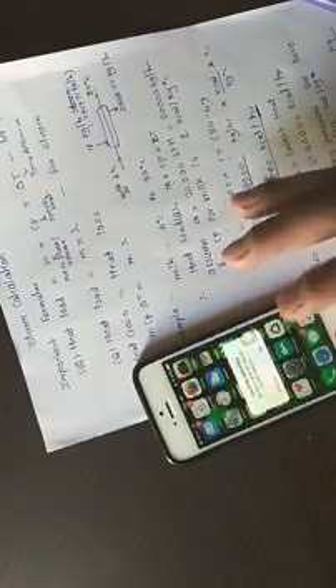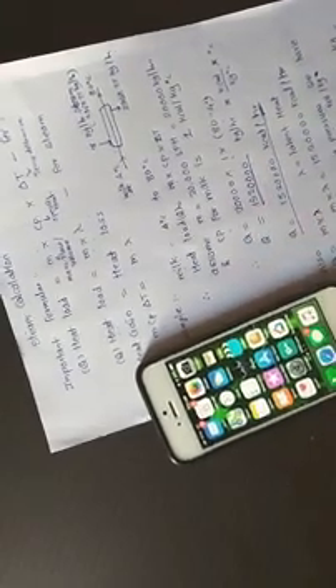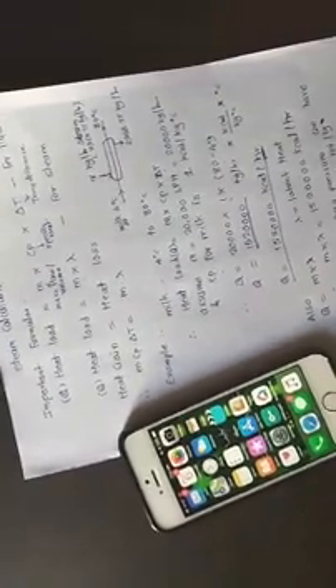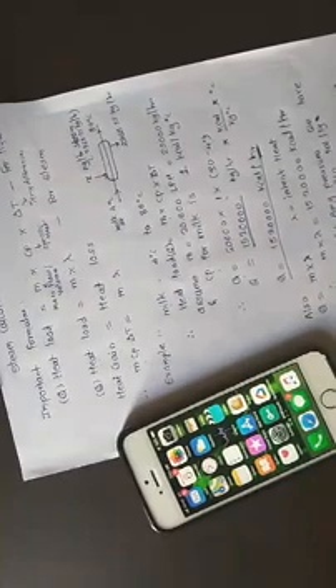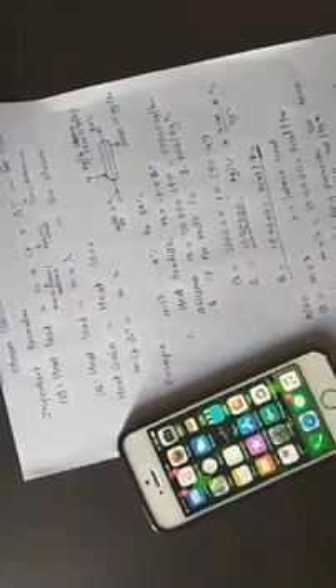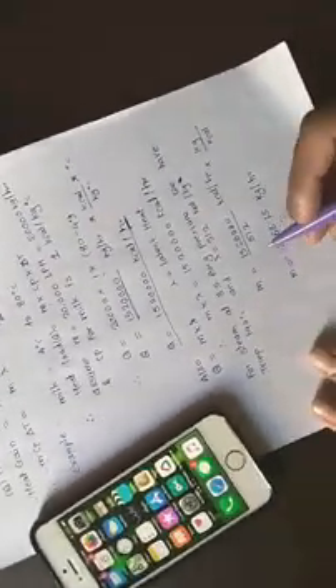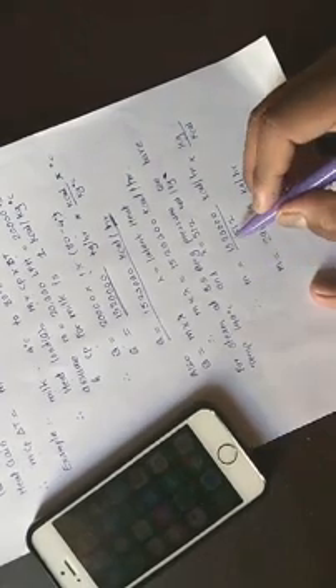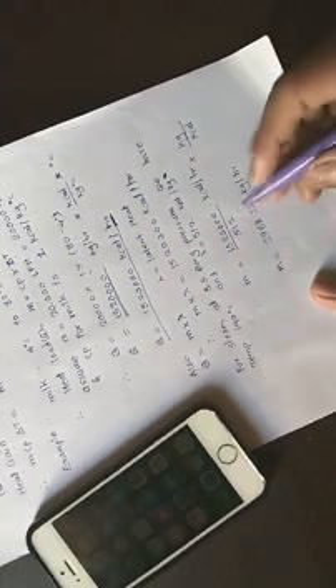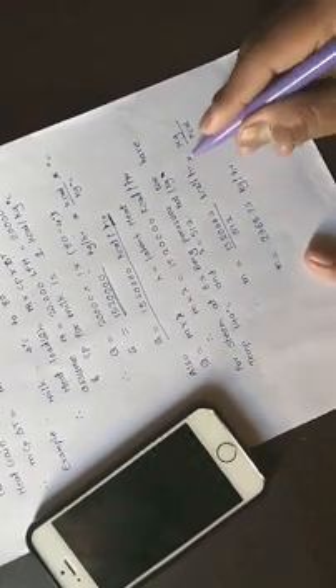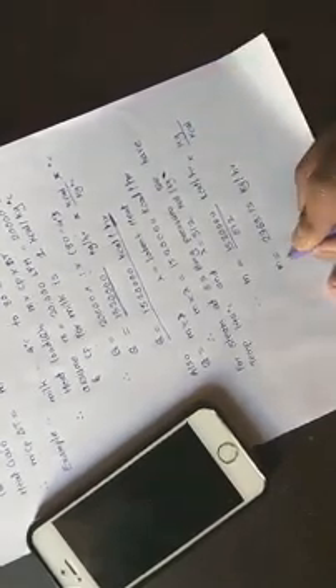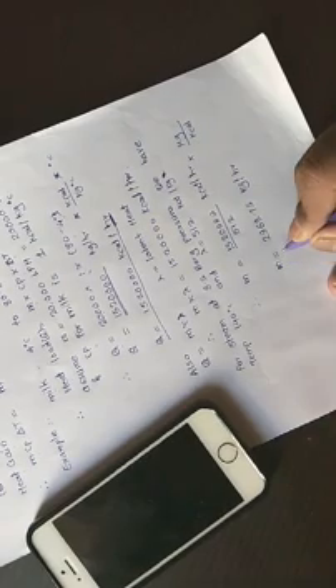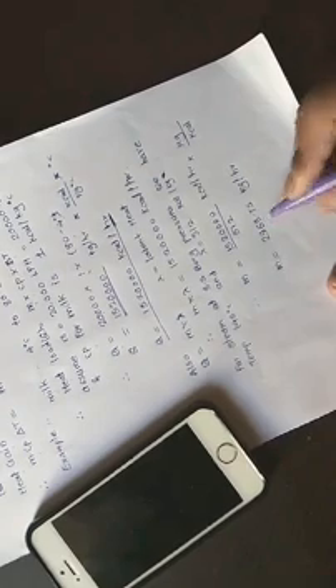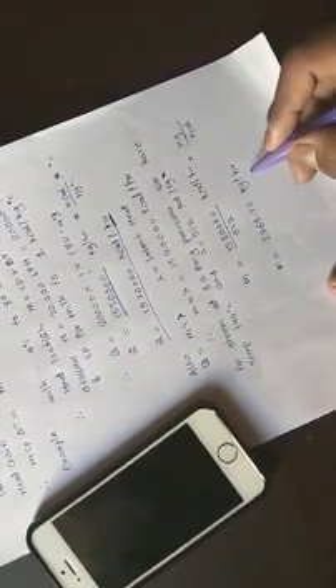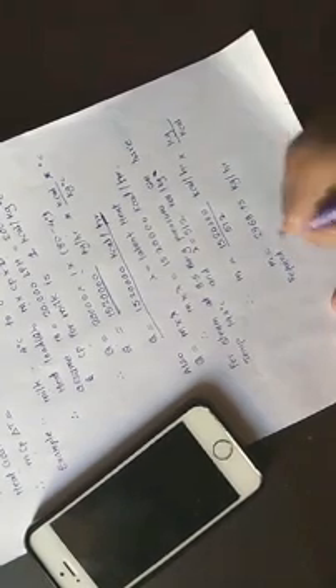Okay, let us continue. Now I have calculated, but later I will show you the tool. So we have lambda equal to 512 kilocalories per kg. When we equate this value with our steam load, then M is equal to this heat load from the product side divided by 512 kilocalories per kg, those are the units. So now you will get the steam flow rate which is required to achieve our duty. So M is equal to 2962.75 kg per hour, that is the required steam flow rate.